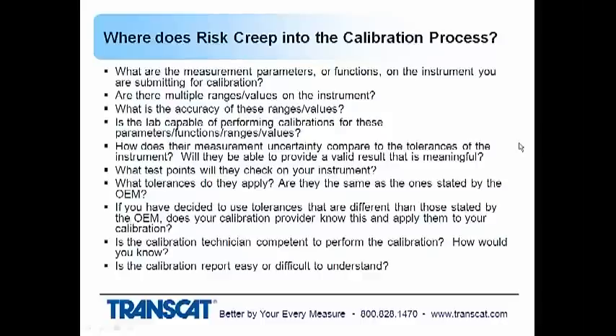And then you've got to look at the lab that you're sending it to, whether it's an internal lab or an external commercial lab. Are they capable of measuring in those parameters or those functions or ranges or values? How does their measurement uncertainty compare to the tolerances or the accuracy that we talked about above of the instrument? Will that lab be able to provide valid results that are meaningful to you? If their uncertainties are as large as the tolerances of the instrument, is there any value to that? Certainly their uncertainties need to be significantly smaller.